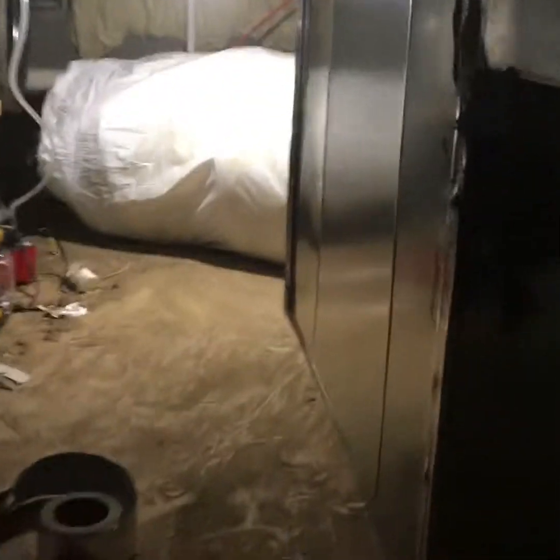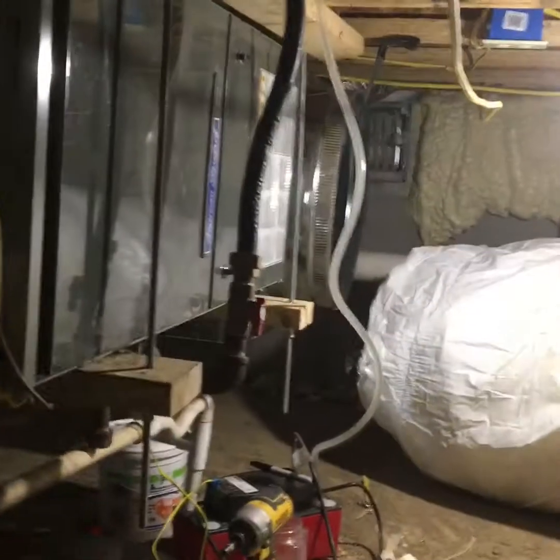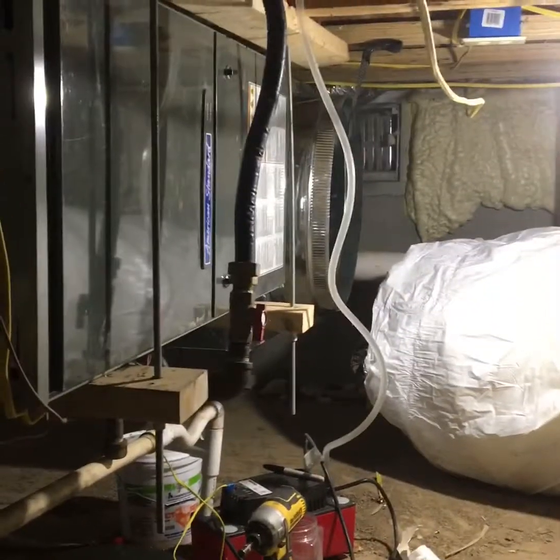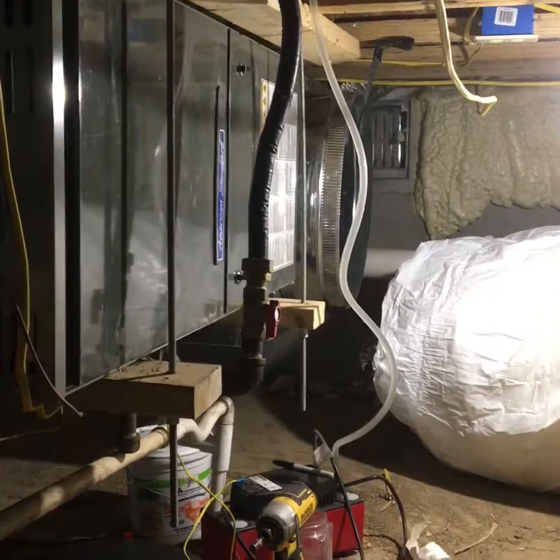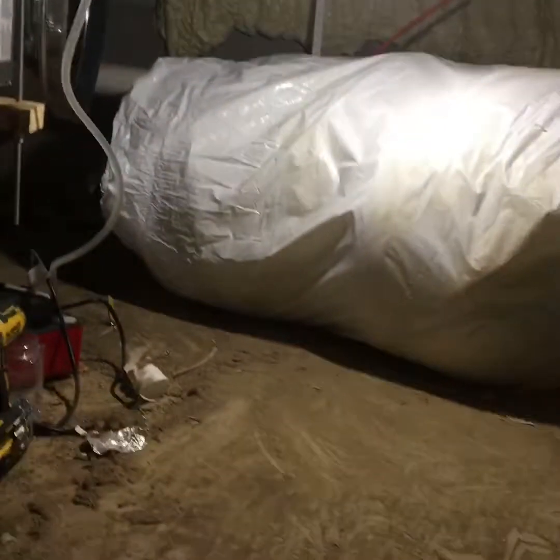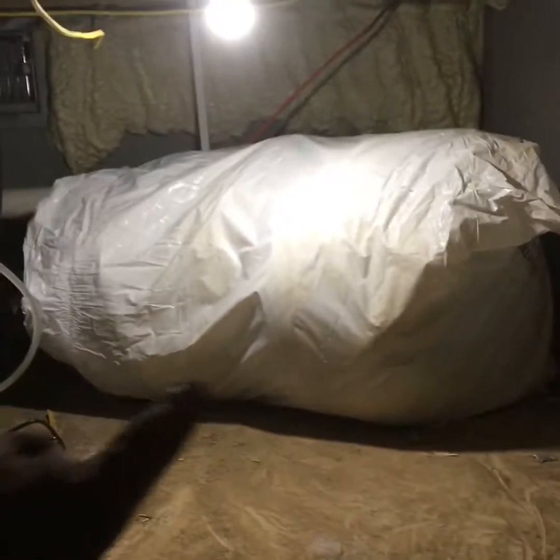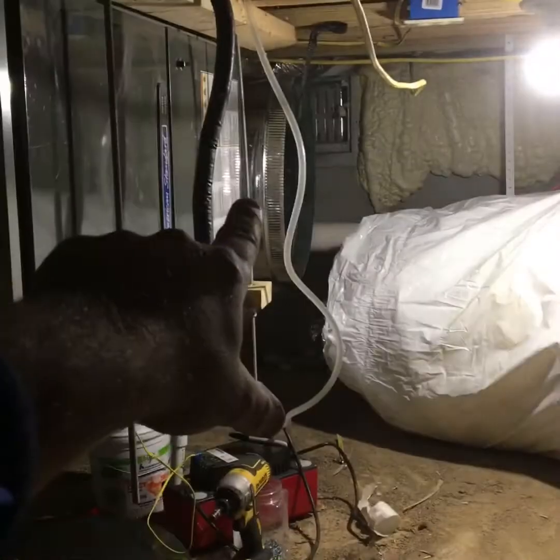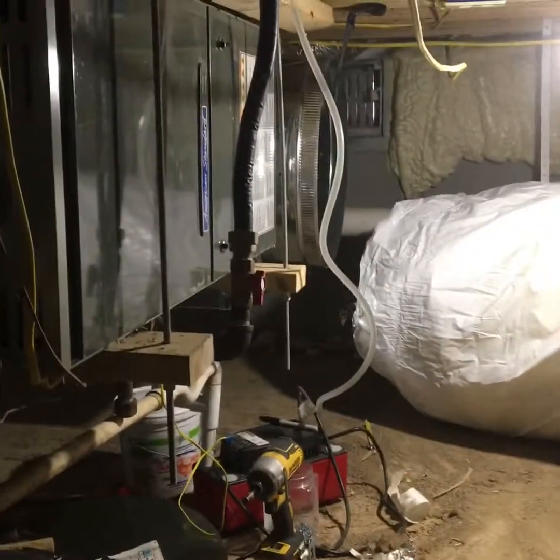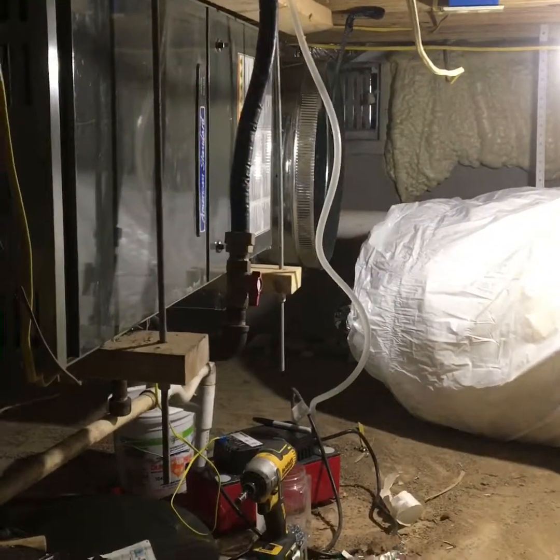So I had some 24 by 24 boxes made. Whenever I'm doing a repair like this, those are pretty handy because they'll fit on the back of any HVAC system. We can just cut those into our flex. We're going to run some 20-inch flex. I had some, and so I'm just going to use it and come around to the box here on the back of this American Standard, and that's going to give us the airflow we need back to this unit.